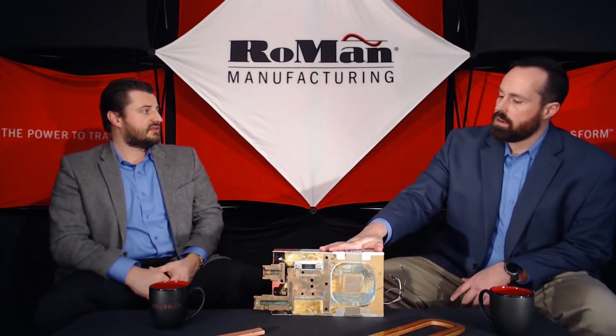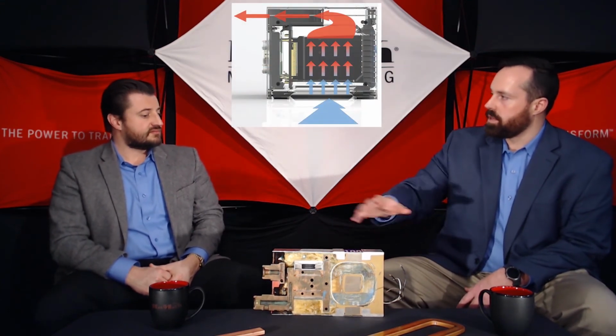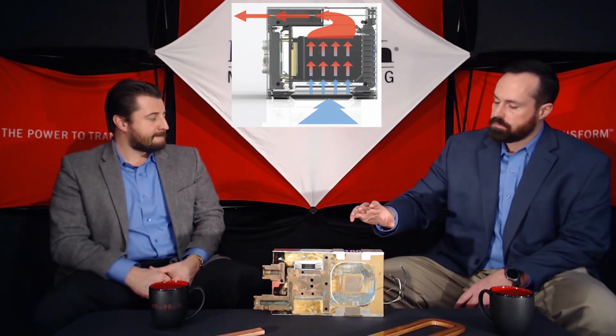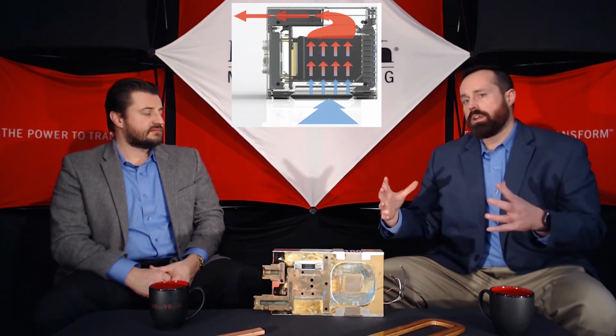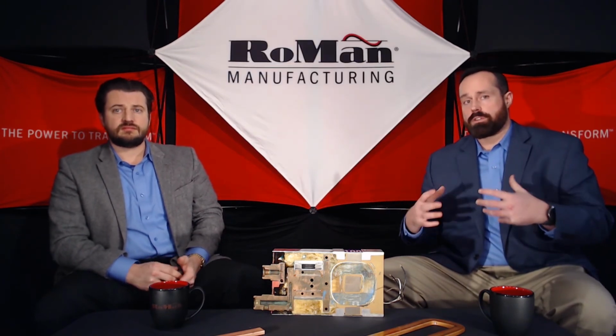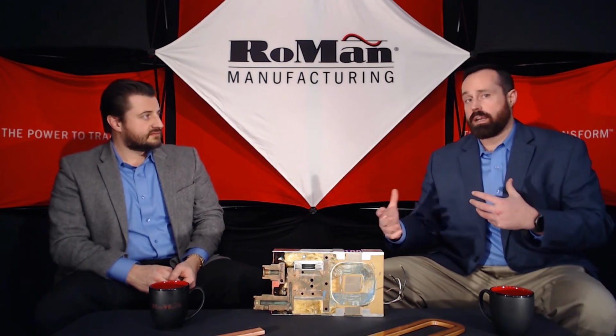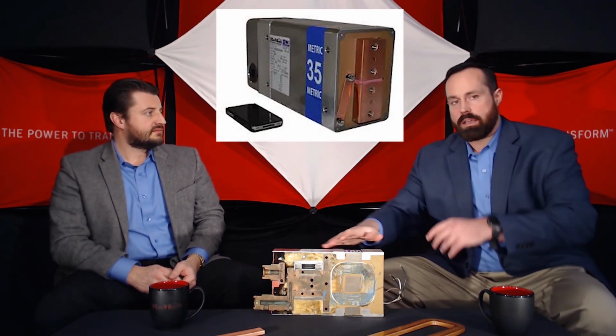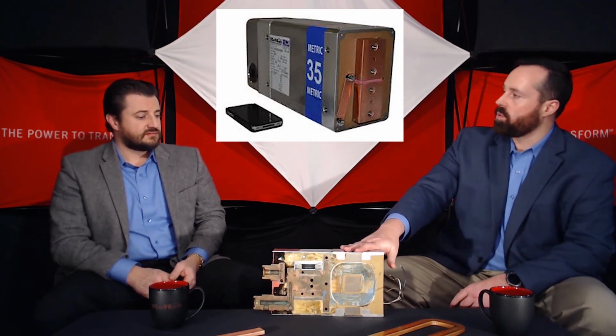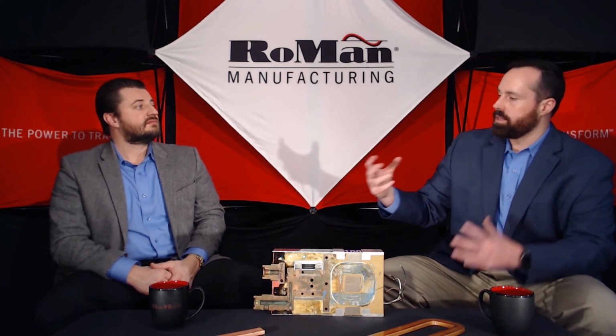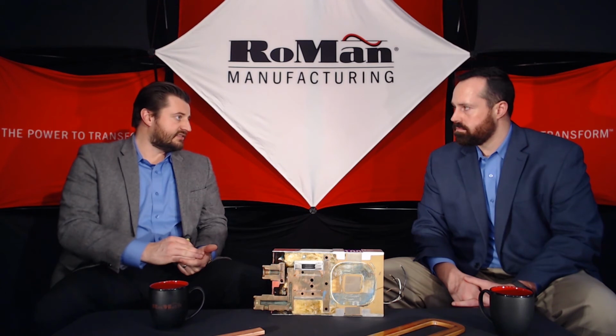So imagine an air-cooled transformer and the channels in which the air has to flow through the transformer. The larger area within a transformer forces you to use more magnetics or core to transfer the same amount of electromagnetic energy. When we use water cooling, we're able to make our transformer so much more compact. And when we make it more compact, we can use smaller magnetics and really shrink the footprint of it. So it's a whole different type of philosophy of design. Water itself is significantly more efficient than air to cool a transformer, and it also makes the transformer itself smaller. Okay, that's very interesting.